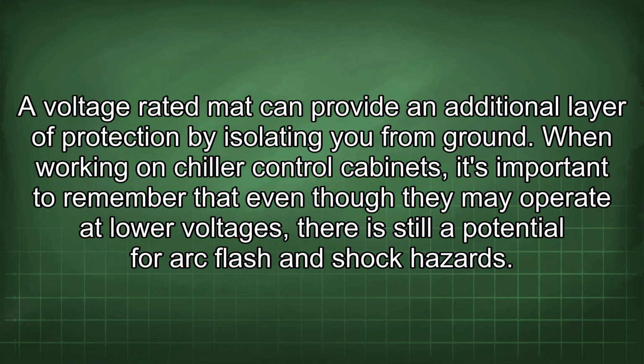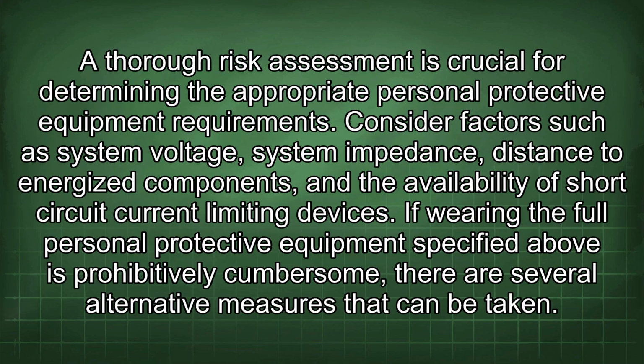When working on chiller control cabinets, it's important to remember that even though they may operate at low voltages, there is still a potential for arc flash and shock hazards. A thorough risk assessment is crucial for determining the appropriate personal protective equipment requirements. Consider factors such as system voltage, system impedance, distance to energized components, and the availability of short-circuit current limiting devices.